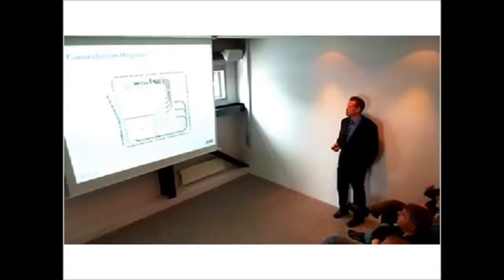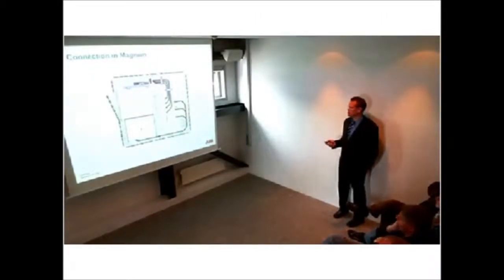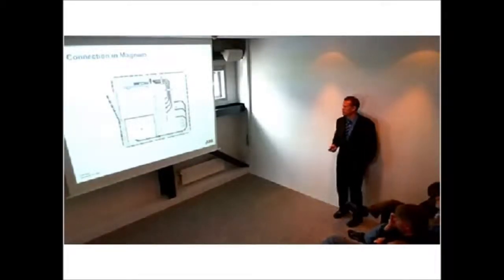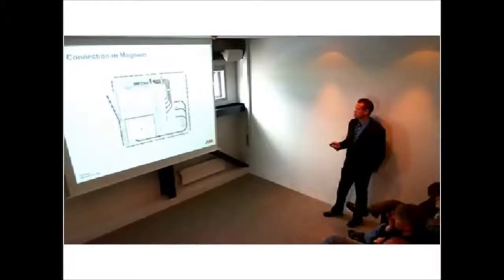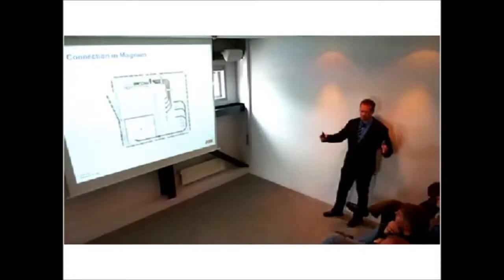This is Magnum 250 with these cable clamps mounted. We have brackets that we can mount directly to the transformer, and of course on the wall we have wall brackets. So this is a short distance. What's important is that you have every cable in the same phase. If you have 2, 3, 4 pairs of cable, the length of the cable should be the same for each phase.